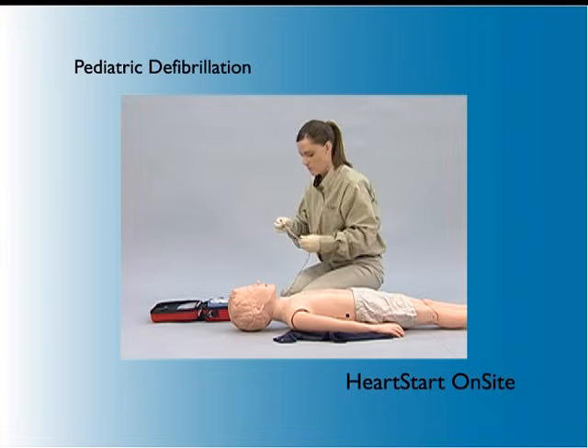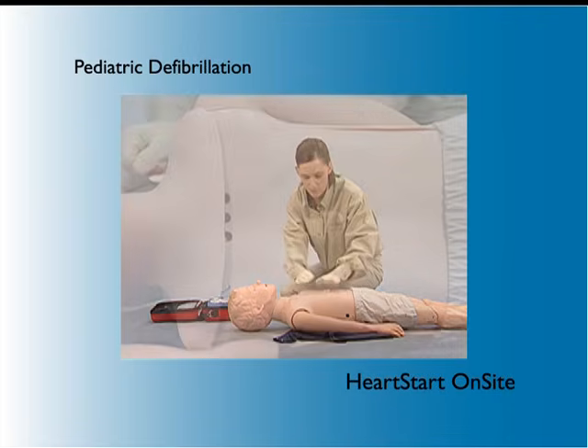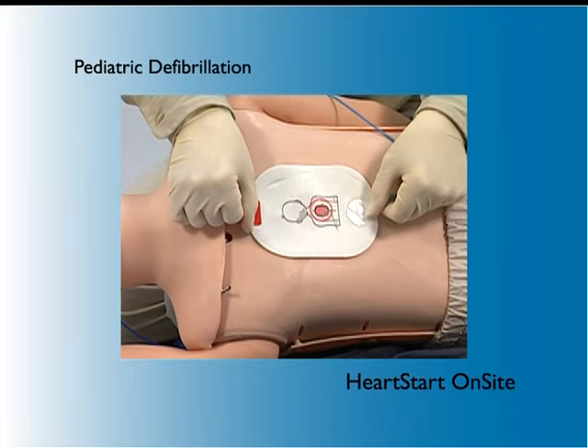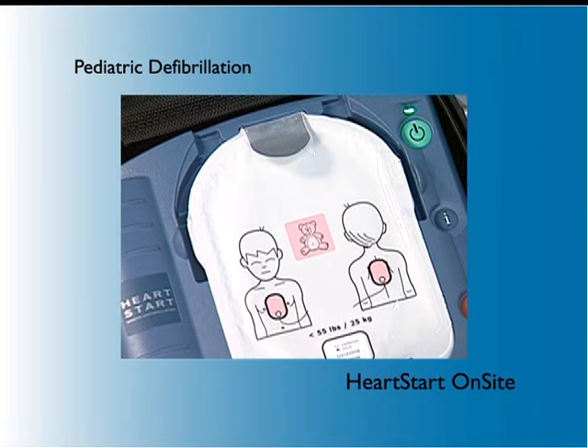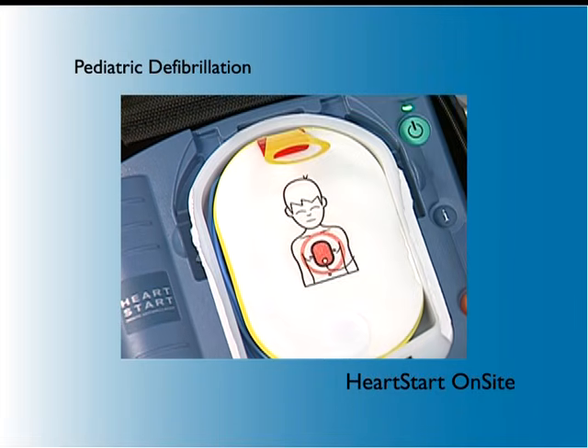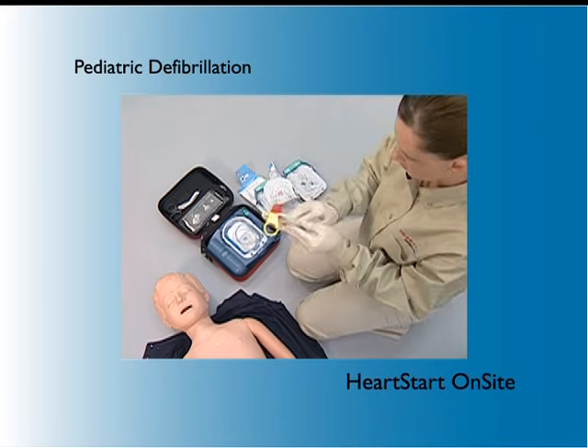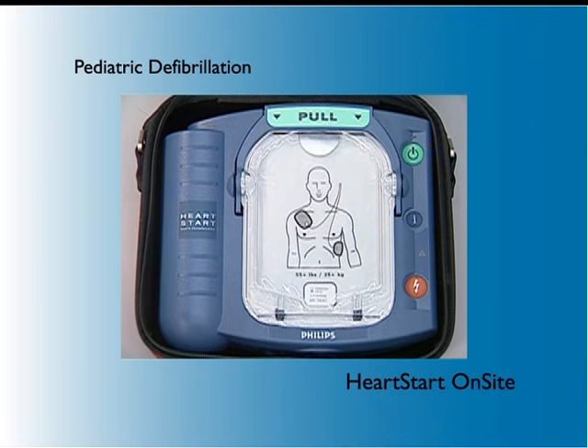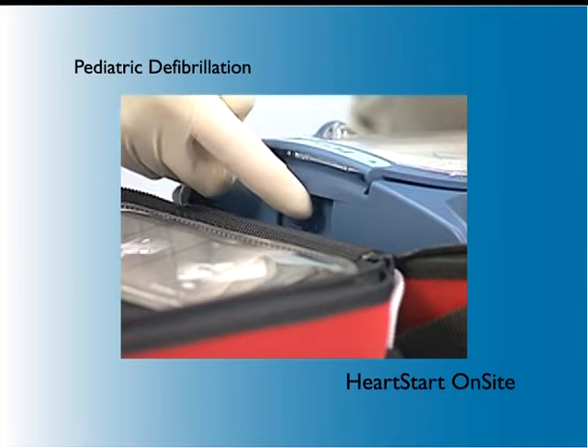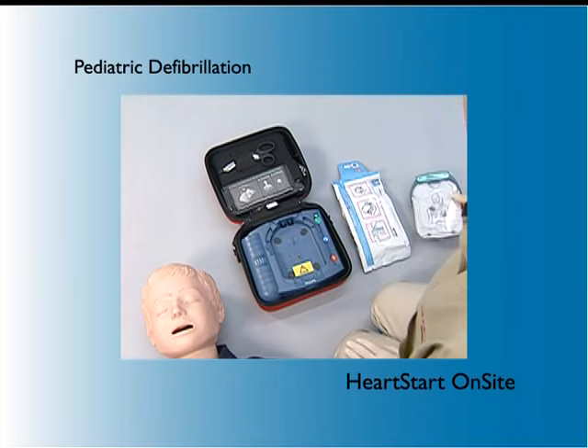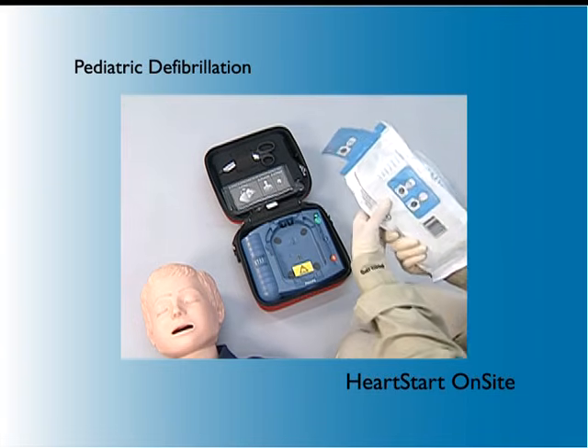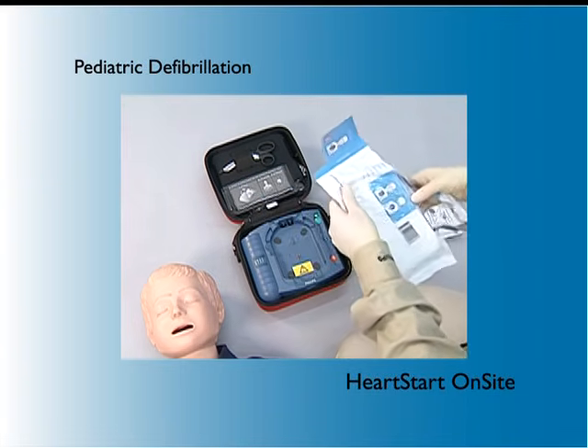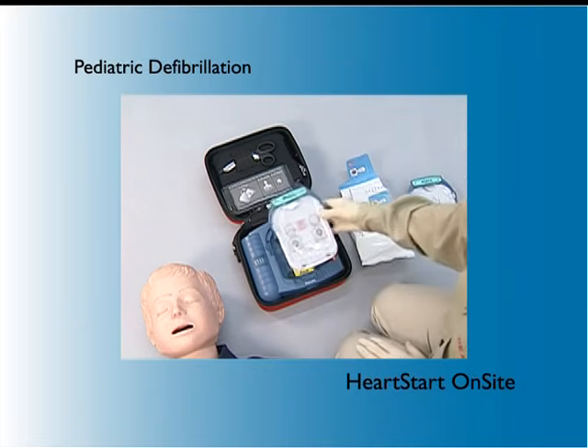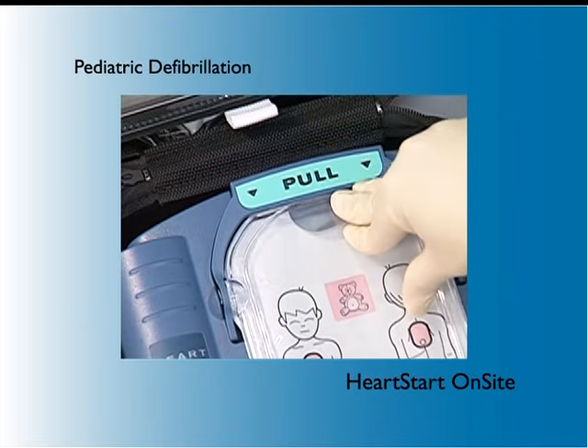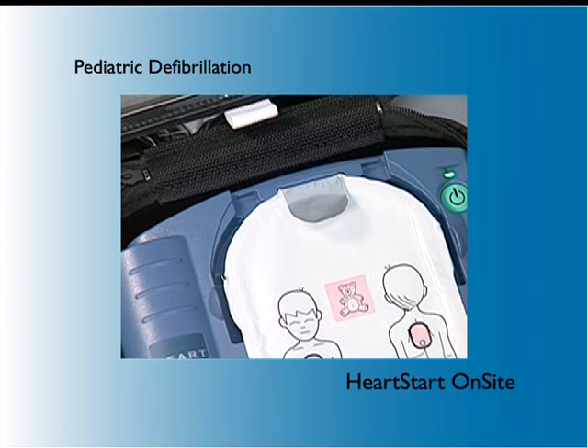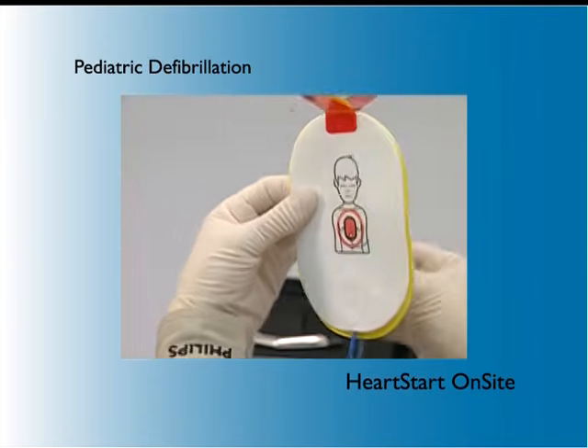The On-Site can be used to provide reduced energy defibrillation of infants or children under 8 years of age or 55 pounds. The On-Site uses an infant-child PADS cartridge. If the infant-child PADS cartridge is available and not already installed, remove the adult PADS cartridge from the On-Site by sliding the latch at the top and lifting out the cartridge. Remove the infant-child cartridge from its packaging and install it in the defibrillator. Be sure to press the cartridge down until it latches into place. Then pull the green handle to begin the rescue. PADS placement is illustrated on the back of each pad.